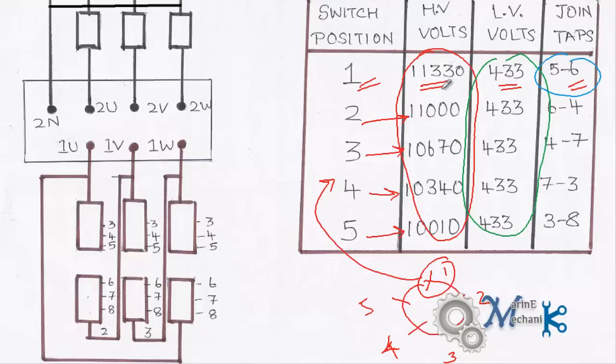So what happens is position number 1 joint tap 5 and 6, which means here you can see tap 5 and tap 6. So these two get connected and the HV side windings, these two windings are engaged. So the number of windings actively involved in transformation process varies. That's what it means.